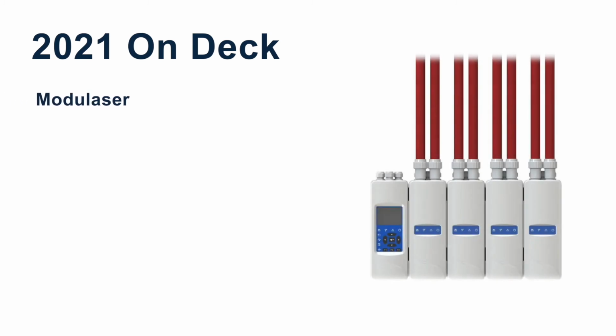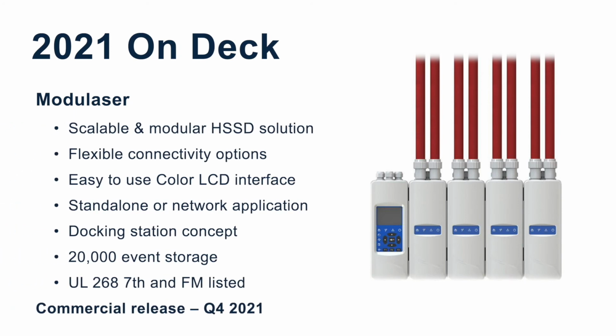The last program we are expecting this year is a new offering in our AirSense products with the addition of Modulaser. This new aspirator provides flexible scalability that can go from 1 area of protection to 4 areas by simple interconnection. Aspirating modules can also be remote mounted from the command module to put the unit close to the monitored area to reduce pipe length. The command module has plenty of room for storing events and features a color LCD for user friendliness. This product will replace the current ASD 320 and ASD 640 products. This product will be UL 7th edition and FM listed upon release.